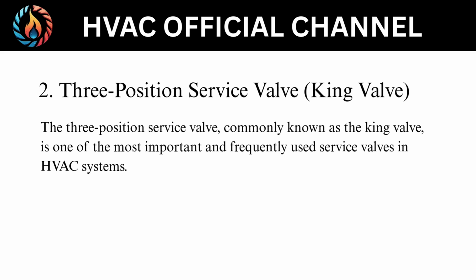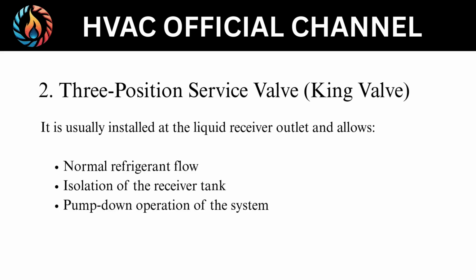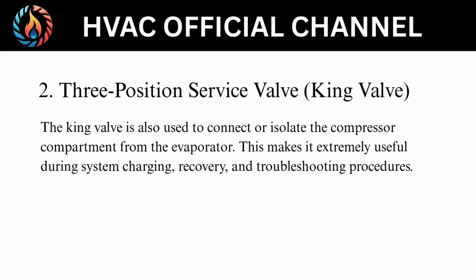2. Three-position service valve, King valve. The three-position service valve, commonly known as the King valve, is one of the most important and frequently used service valves in HVAC systems. It is usually installed at the liquid receiver outlet and allows normal refrigerant flow, isolation of the receiver tank, pump-down operation of the system. The King valve is also used to connect or isolate the compressor compartment from the evaporator. This makes it extremely useful during system charging, recovery, and troubleshooting procedures.